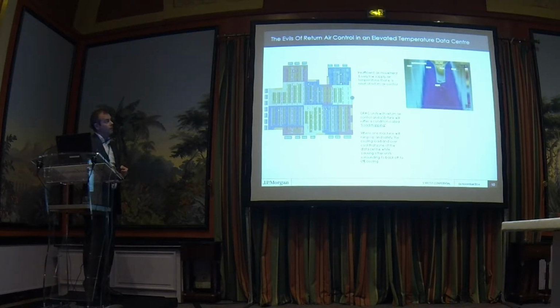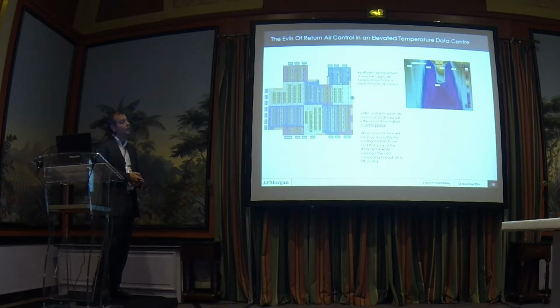So, can anyone tell me what's wrong with this picture? Absolutely freezing there. It's down there, hardly anything. You're under about, well, I'm guessing probably about 20, 22 or something degrees. There's a cabinet here, there's a cabinet there, there's also another cabinet just here outside the picture. But in here you can see that the airflow all seems to be coming up through the middle. This was to do with all the floor tiles being open.